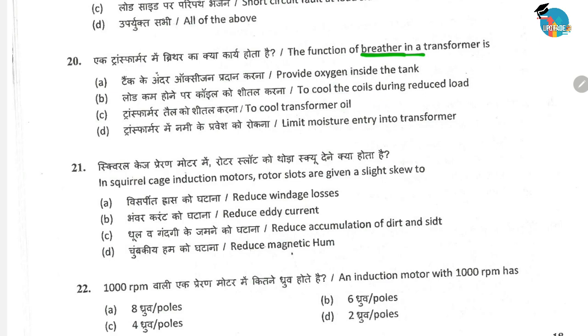Next question is the function of a breather in a transformer is. The options are provide oxygen inside the tank, to cool the coils during the reduced load, C is to cool the transformer oil. The last option is to limit the moisture entry into the transformer. So the function of a breather is to limit the moisture entry into the transformer. Next question is in squirrel cage induction motors, rotor slots are given a slight skew to. It is given a slight skew to reduce the magnetic humming. Correct option is option D.